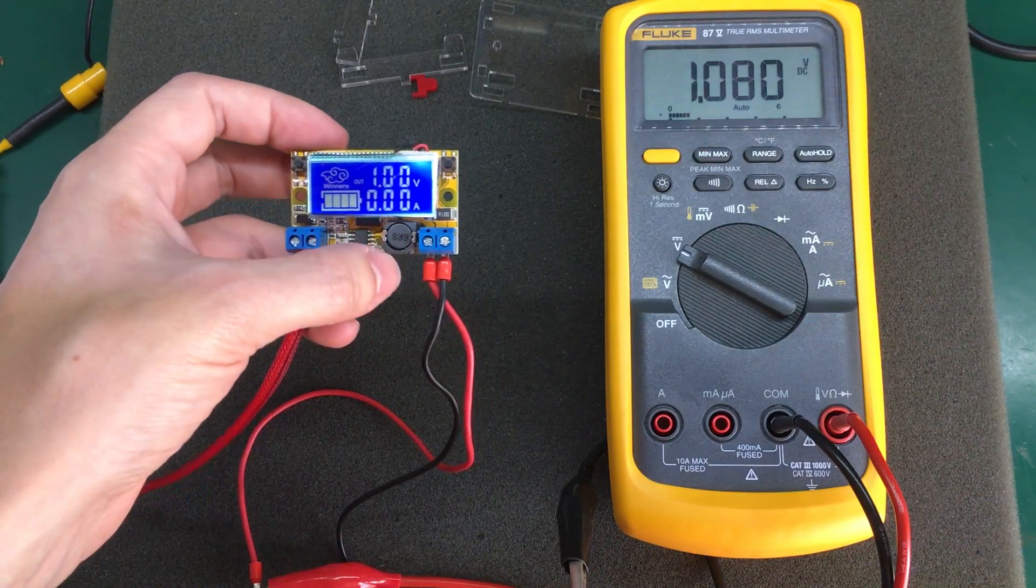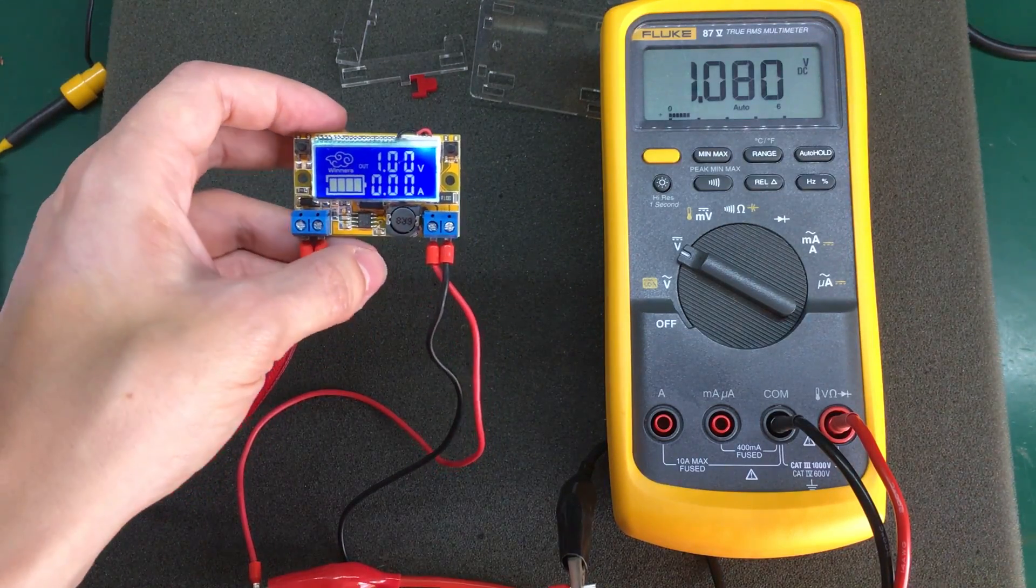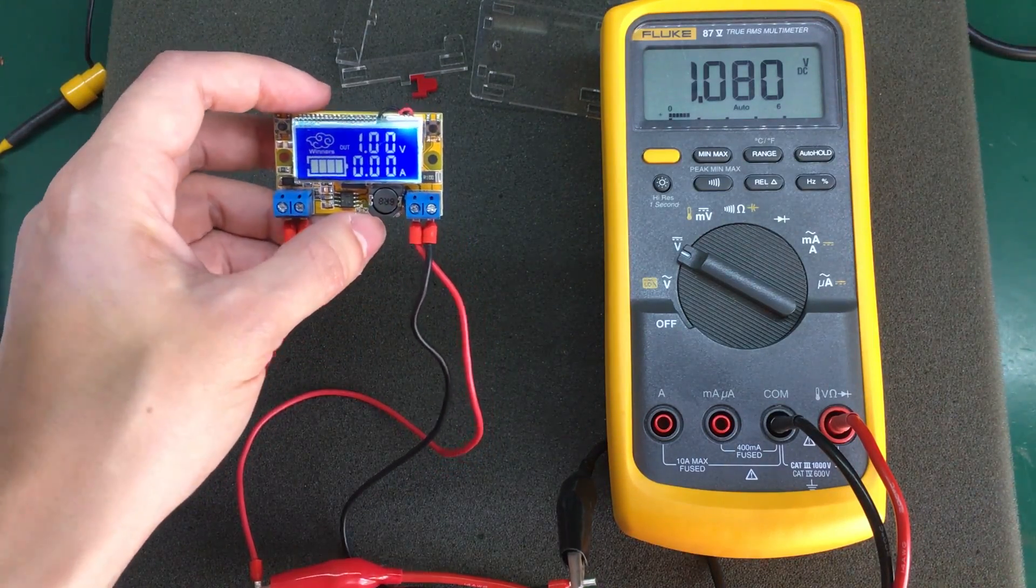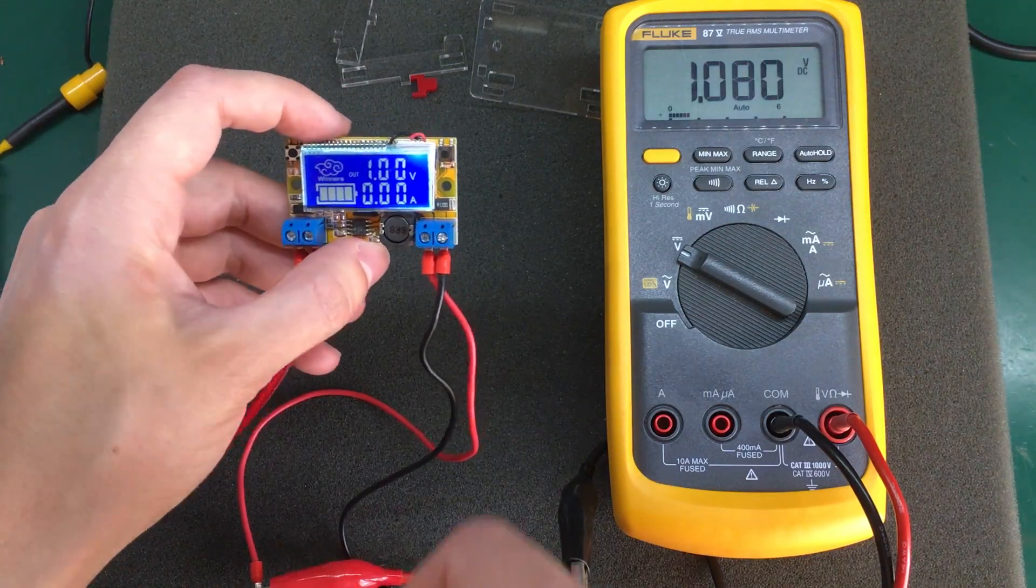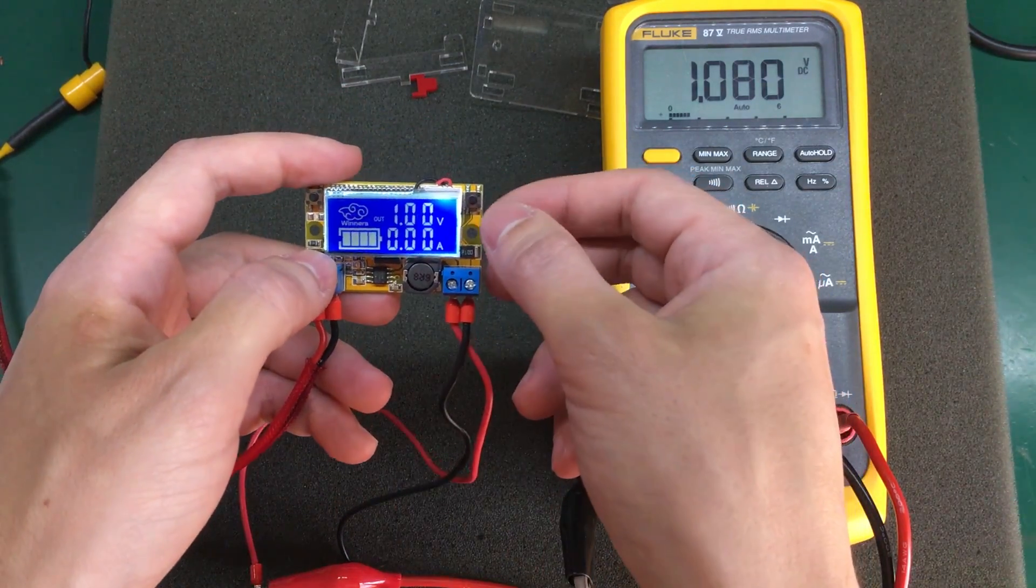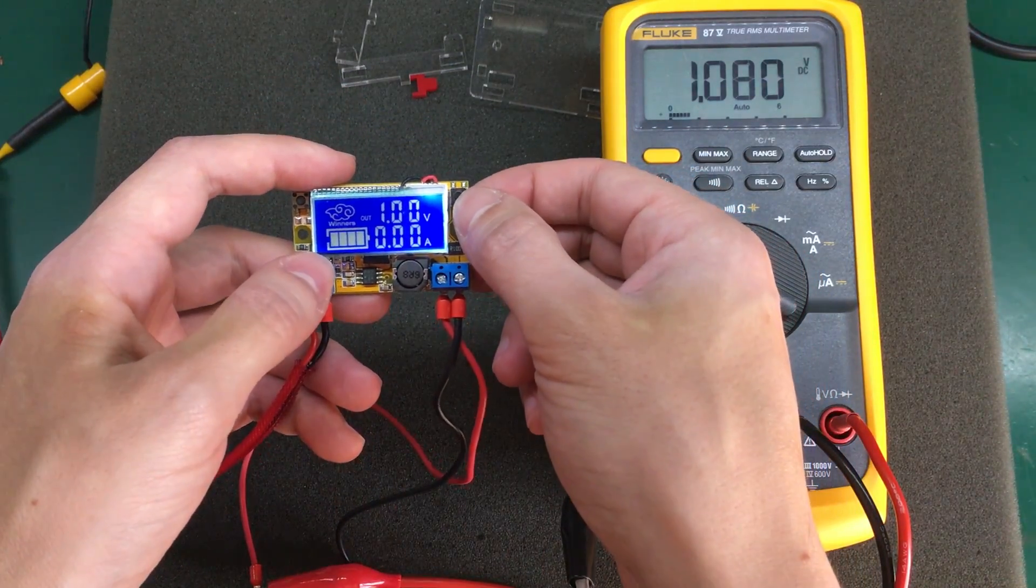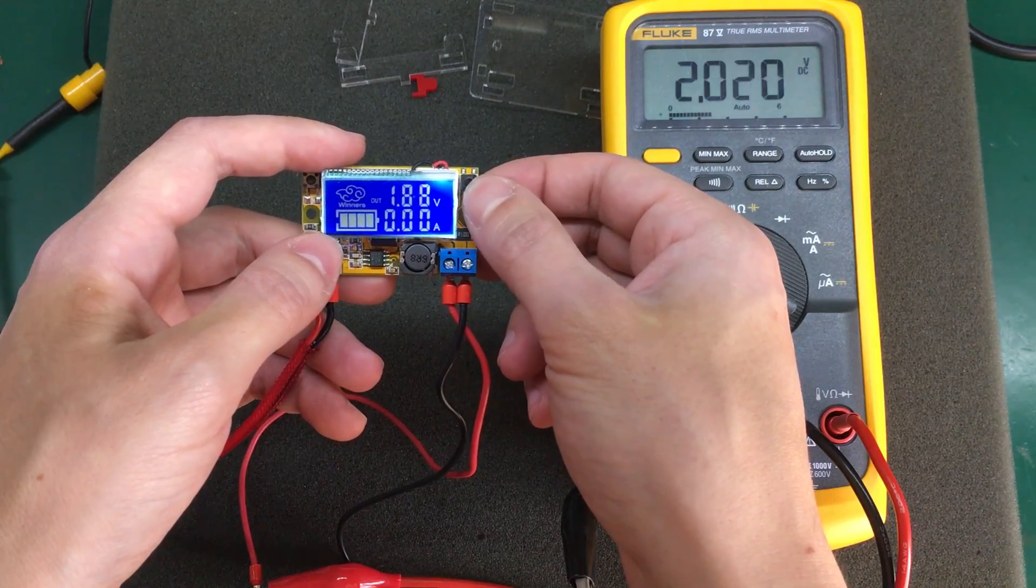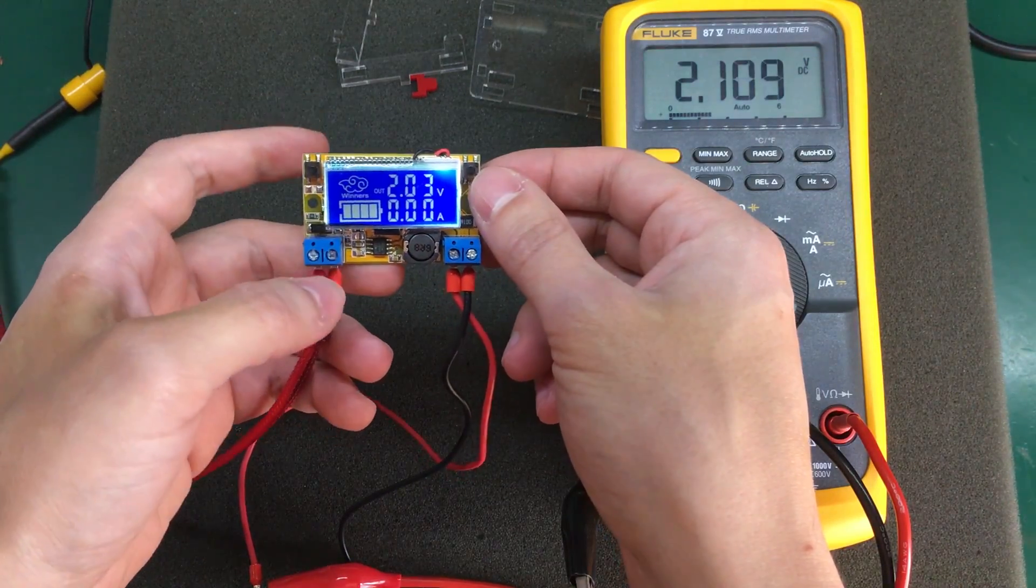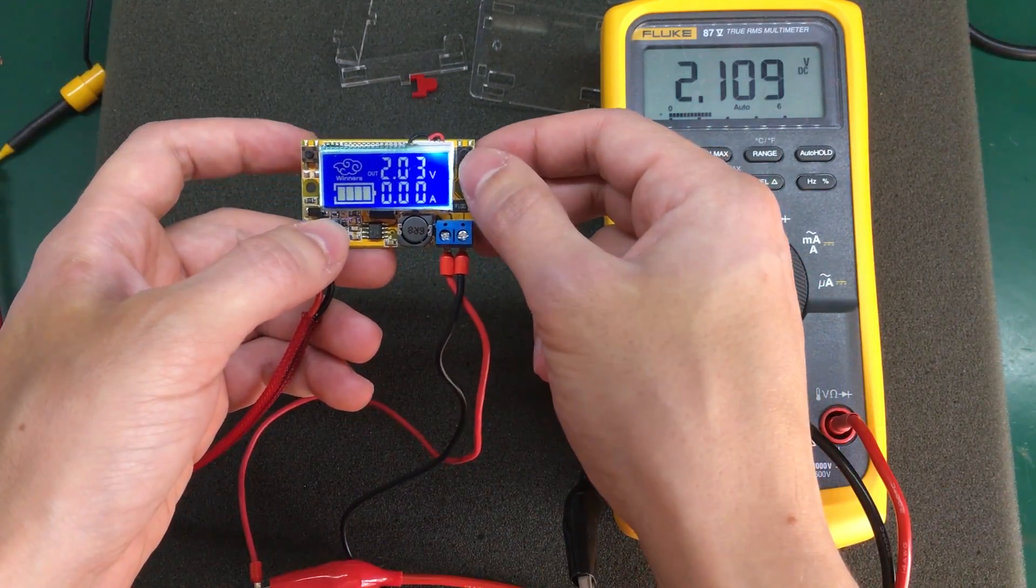I have it set for 1.00 volts and showing 1.08 on the Fluke. So about 80 millivolts error. Let's go to 2 volts. The error increased a bit.